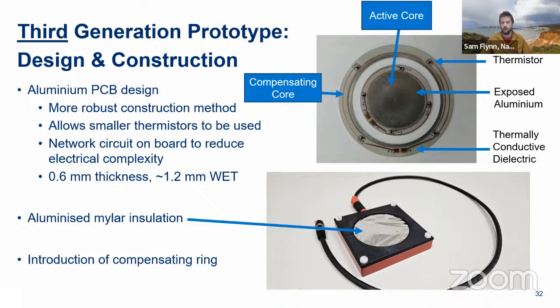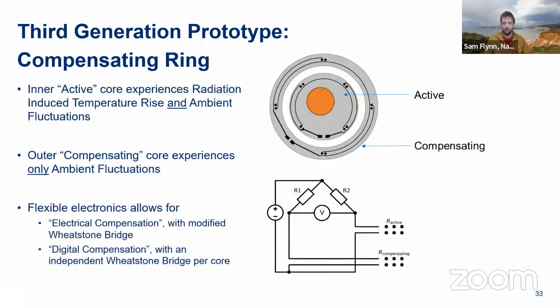This also has a secondary, we call it a compensating ring, around the outside. So we've got a central core region, which the beam goes into, but then we've got a halo around it. These two regions are designed to have the same area, so they're exposed to the same amount of air turbulence or infrared contamination. But if you only put beam into the active one, you can start to isolate the signal between one and the other.